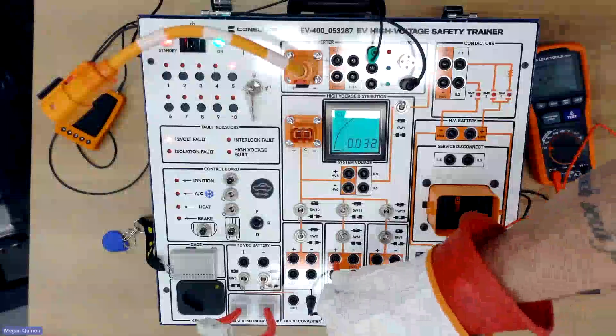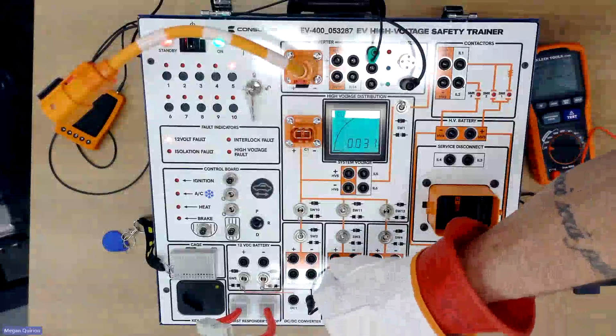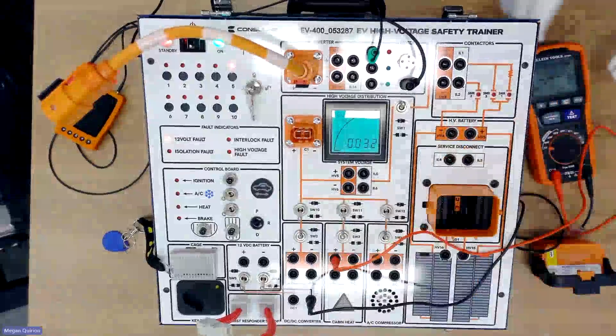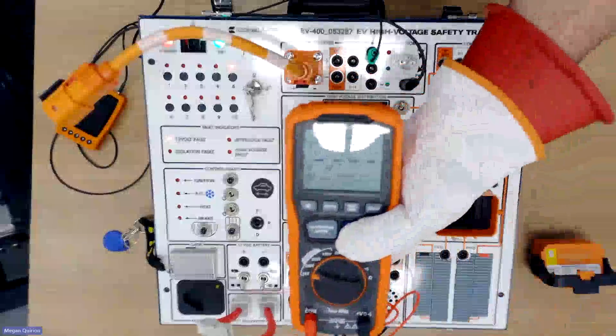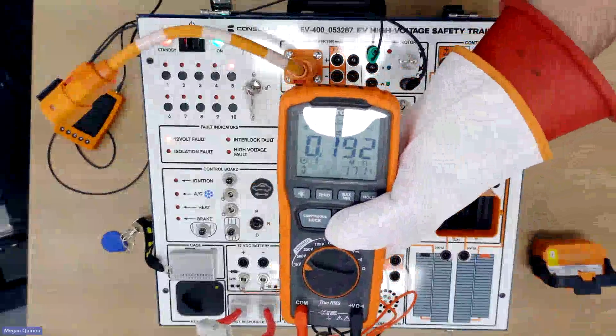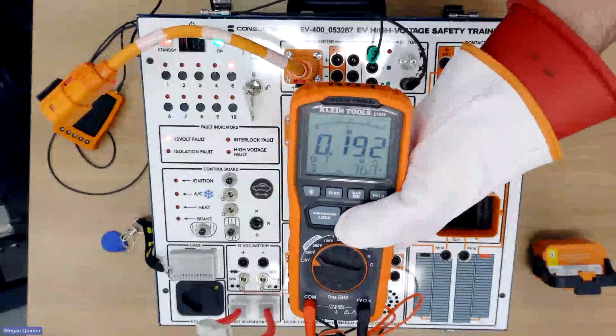Just to show what it looks like when you have an isolation fault using your isolation tester, he's going to apply the same 1,000 volts to the component. As you can see, when he activates the test, the reading is a lot less than the 4,000 megaohms he had earlier.